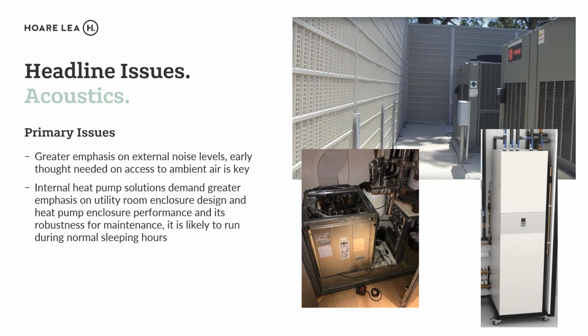Acoustics, I've mentioned before, not just externally, obviously with airborne noise to adjacent residences or amenity space, but in particular if you go for in-apartment heat pumps, the heat pump itself needs to be acoustically treated and the utility cupboard well designed with regard to its enclosure, because these heat pumps will probably generate hot water at night. Siting that utility cupboard in its correct location away from bedrooms matters, as it can become extremely problematic if you start including heat pumps in the very quiet spaces of a residence.